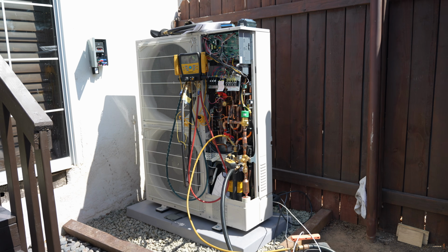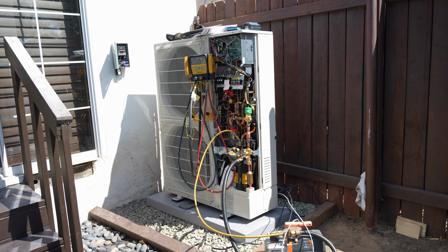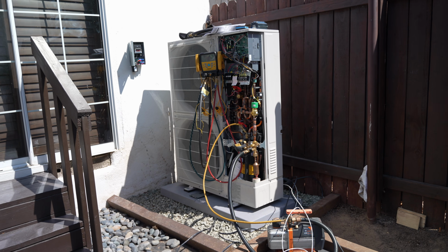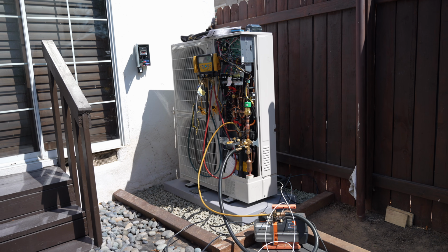What this means for you is extremely consistent indoor temperature, a very quiet operation, high efficiency, excellent humidity control, and long steady run cycles instead of on-off cooling. These systems are designed to maintain comfort very precisely. The downside with these systems are the highest upfront cost, more complex electronics, and they are going to require proprietary thermostats and controls. Our next group is multiple stage or inverter systems.